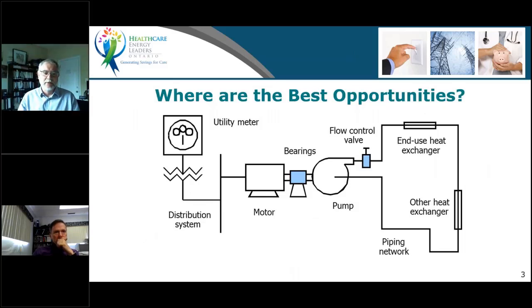Here we have a pumping system which is provided with electricity from a utility meter via a distribution system. We've got the motor which converts electrical to mechanical energy. We have a close coupled motor to a pump, or pump to a motor. We've got the bearings in there. Then we have the pump, the centrifugal pump is shown, which creates flow in a loop. And ultimately we need flow between those two heat exchangers to move heat from the source to the sink heat exchanger. But in the middle of all that, in addition to the pump, we've got a flow control valve of some sort. Even if it's fully open, it might be introducing a bit of friction in there. And we have a piping network.